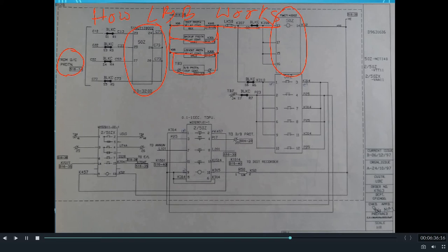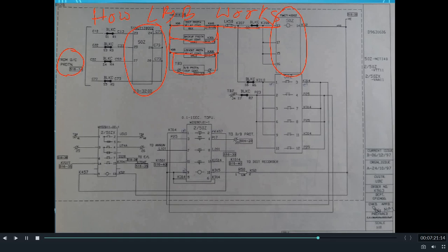Looking at the operation of LBB, the DC supply to the LBB relay will be through only when the main protection relay, the backup protection relay, lockout protection relay, or the busbar protection relay operates. But in normal condition, on operation of any such protection relays, the circuit breaker of the particular feeder will trip, and as a result the current flowing through the feeder will stop. Hence, in normal condition when there is a fault in the feeder, the DC will be supplied to the LBB relay, but at the same time the current through the LBB relay will not be available since the circuit breaker will trip immediately. Hence, the LBB relay will operate only when the DC supply to the LBB relay is present as well as current through the LBB relay is present — a situation only possible when the circuit breaker does not operate despite any of these protection relays actuating.